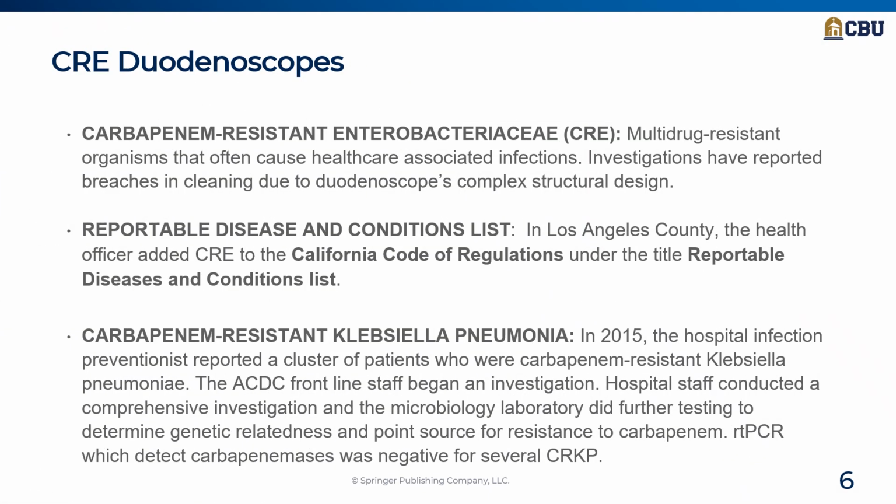CRE became a major concern when outbreaks were linked to ERCP procedures, endoscopy procedures. Investigations found that even when cleaning protocols were followed, the complex design of the duodenoscope, especially the elevator channel, made complete disinfection very difficult, allowing resistant bacteria to spread. In Los Angeles County, CRE was added to the list of reportable conditions to strengthen surveillance efforts.